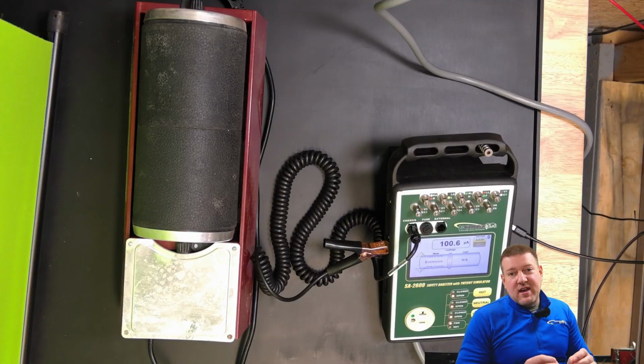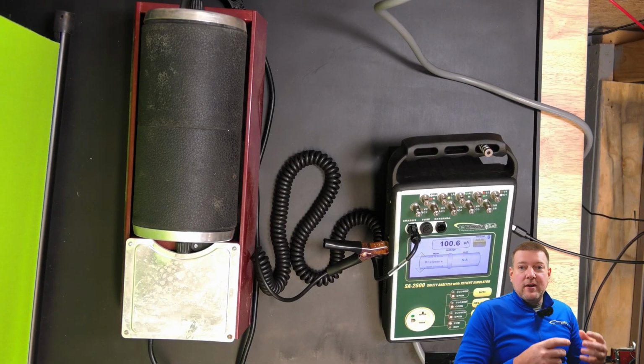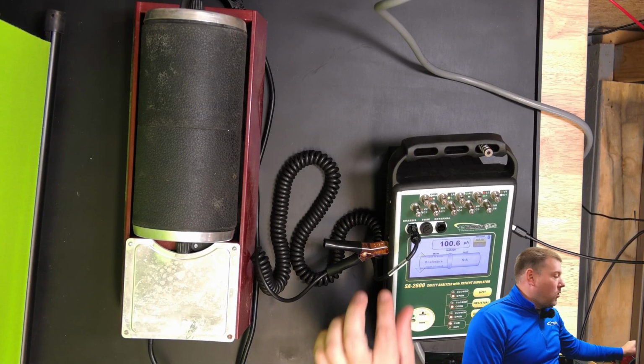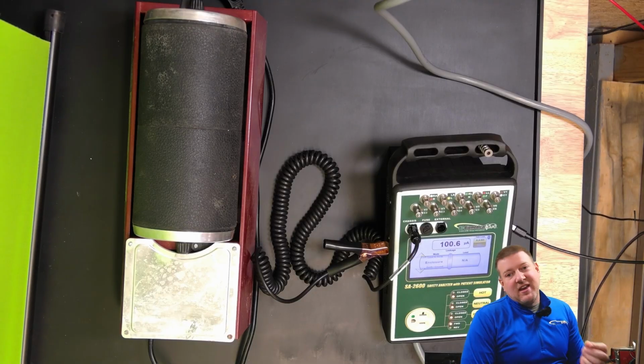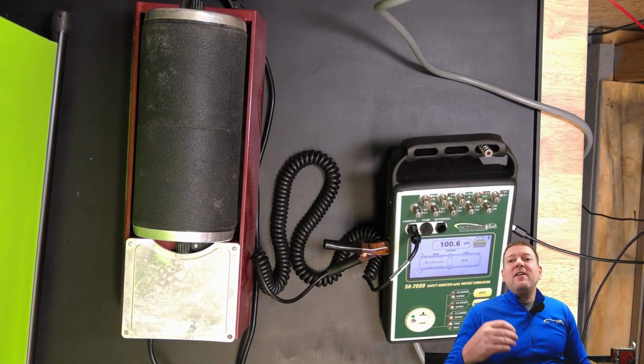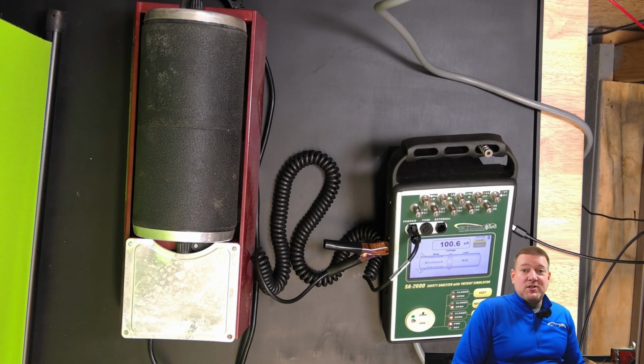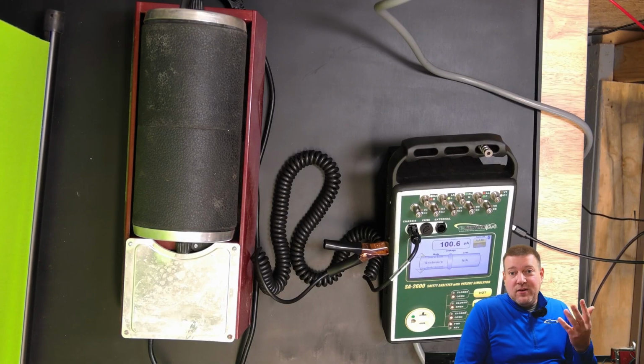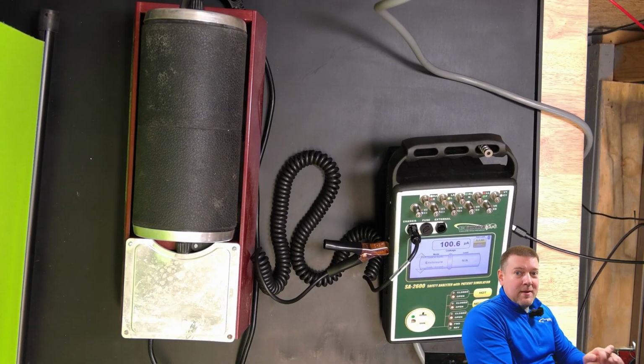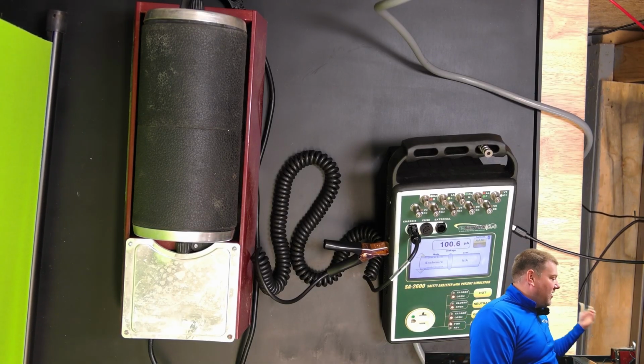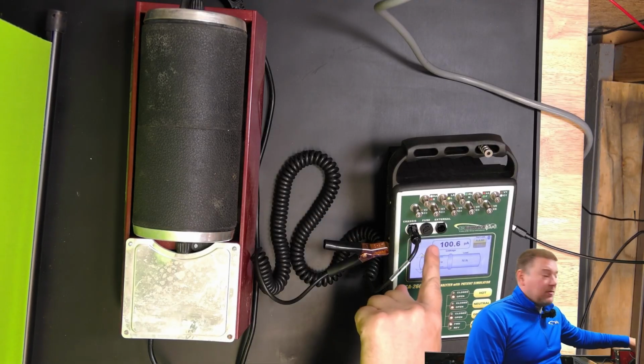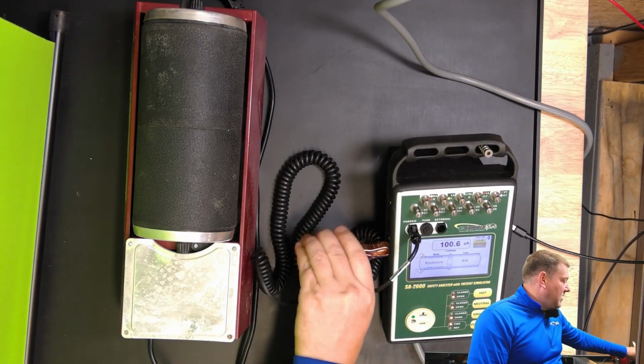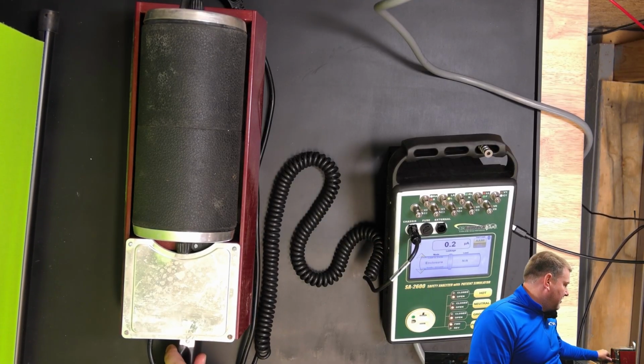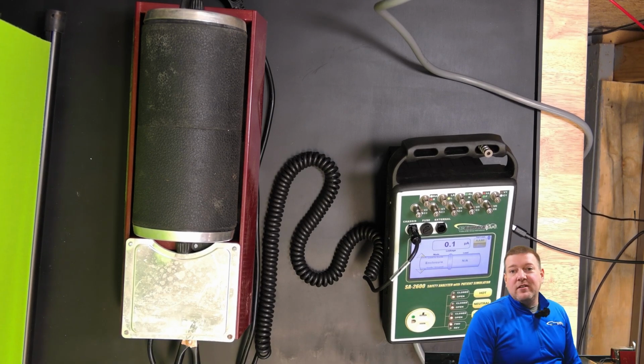So the first test we did was testing the continuity and the ohms of the test lead. The second test that we are doing is checking the calibration of the meter, because we want to make sure that the meter knows exactly what a calibration value should be, because we want to measure leakage. 100 microamps, you can see it right here. We're good. So this meter is good to go. Now I know it is safe to use on my next device.